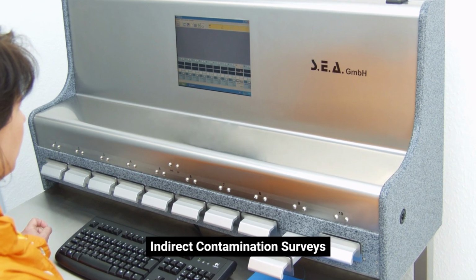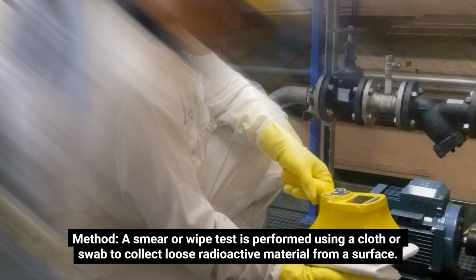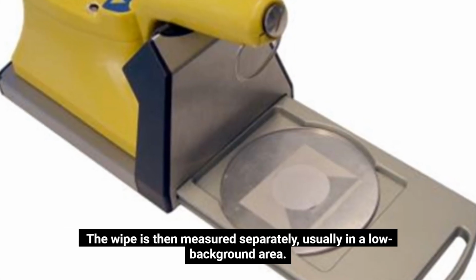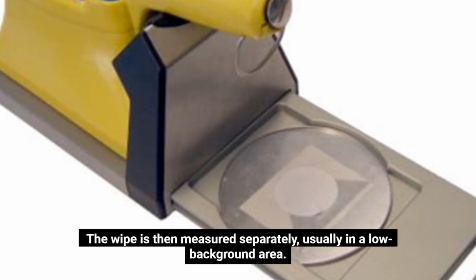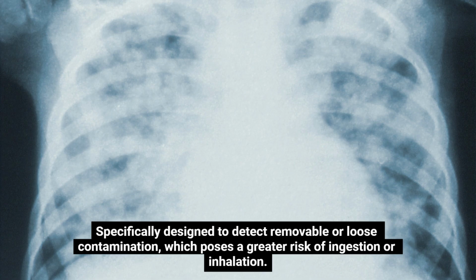Indirect contamination surveys. Method. A smear or wipe test is performed using a cloth or swab to collect loose radioactive material from a surface. The wipe is then measured separately, usually in a low background area, specifically designed to detect removable or loose contamination, which poses a greater risk of ingestion or inhalation.